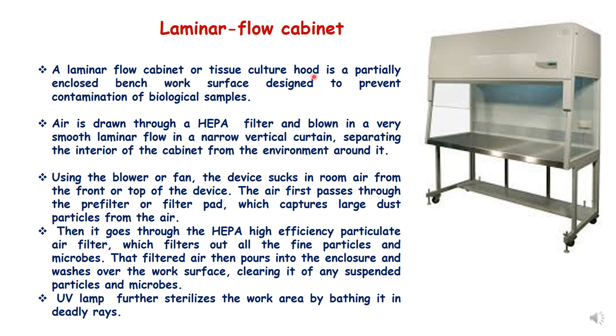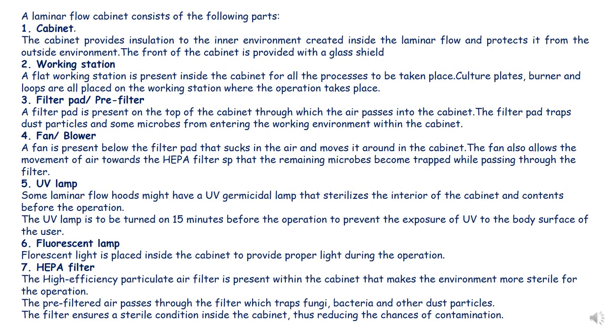A laminar flow cabinet consists of several parts. The first part is the cabinet itself, which provides insulation to the inner environment. The second part is the working station — a flat surface inside the cabinet where all processes take place. The third part is the filter pad or pre-filter present on the top of the cabinet, through which air first passes. The fourth part is the fan or blower, present below the filter pad, that sucks in air and moves it around the cabinet.